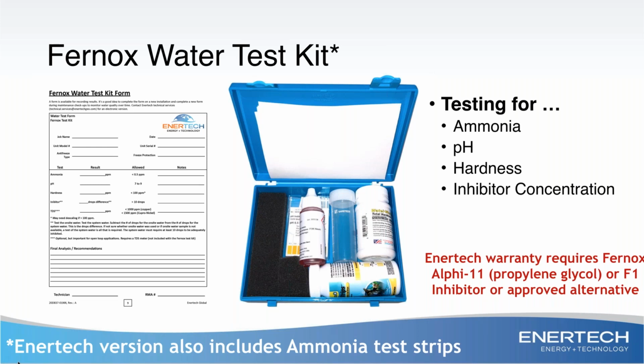Ammonia is in here simply because we have found that unfortunately we're seeing ammonia in rural areas more often than we used to, and ammonia just loves to attack copper, which is prevalent inside these units. So that's never a good thing. So we've added ammonia. The standard Fernox kit does not have the ammonia test. Enertech adds the ammonia test as well as some instructions and a test kit form that you see here on the left. So you're able to record the water quality when you start up that unit, and then you can check that on a regular basis. You don't have to check it as much as you might on a boiler system because the temperatures that we're using are much, much lower. So you may have less time in between adding inhibitor than you might on a high temperature system. You probably want to check it annually at first, but it's quite possible that maybe it only needs checking every 2 or 3 years, depending upon what you start with.